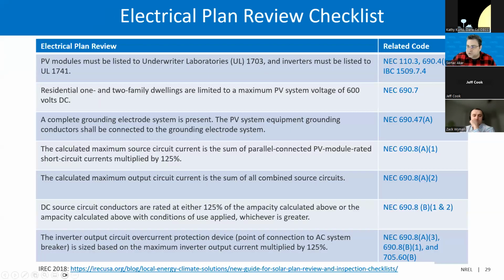And so there are some related codes for the electrical plan review. First, all PV modules must be listed under the UL 1703 Underwriters Laboratories code requirements, and inverters must be listed to UL 1741. That's the first thing to check. And then residential one- or two-family dwellings are limited to a maximum PV voltage of 600 volts DC, and a complete grounding electrode system must be present. The PV system equipment grounding conductors shall be connected to the grounding electrode system.